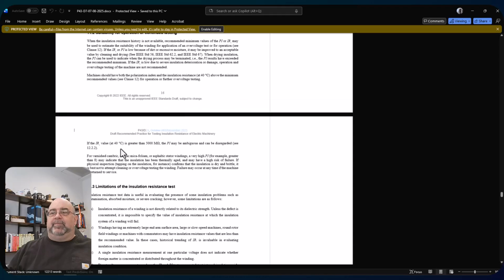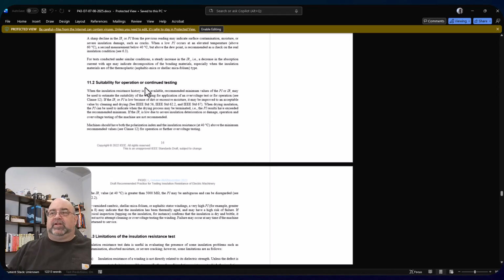Okay? Here are a couple of suitability for continued testing. When the insulation resistance history is not available, recommended values of PI or IR may be used to estimate the suitability of the winding for application of an over-voltage test or for operation. If the IR or PI is low because of dirt or excessive moisture, it may be improved to an acceptable value by cleaning and drying. When drying insulation, the PI can be used to indicate when the drying process can be terminated.